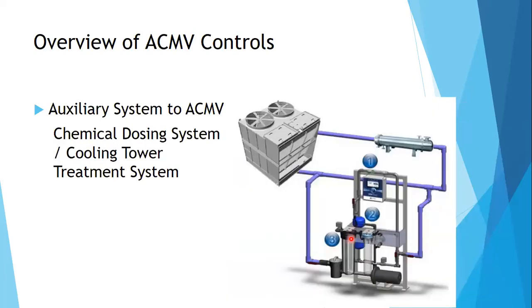Last one, like what we mentioned before, chemical dosing system for your cooling tower. There's a different set of dosing system for your open loop and for your closed loop system. Basically, because your open loop is open to the atmosphere, the dirt and bacteria within the air can also be transferred to your water, which means you would need different chemicals for the dosing system of your cooling tower.